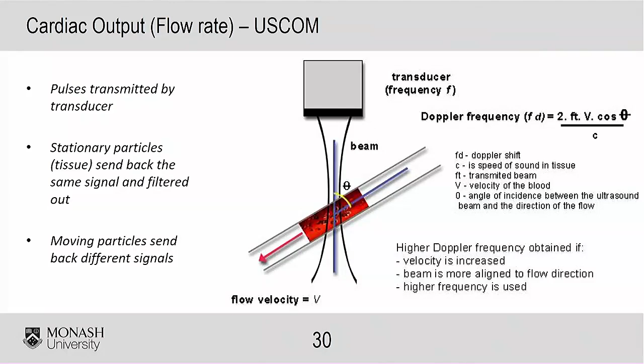And that's something that's important to take away from this message: if you're using ultrasound to determine what your cardiac output is, then it needs to be aligned with the flow, or it needs to have some kind of correction algorithm for misalignment. So basically this is what the USCOM device looks like. It uses that theory. It's based on algorithms from babies that are 23 weeks old up to 86-year-old adults. So its mathematical equations are built in, but it's also being tested in a wide range of patients to correlate it and validate it a lot better than just having those equations alone.